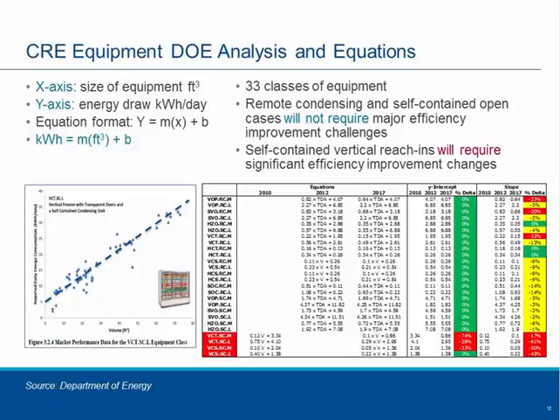Now, a best fit line on the scatter plot follows the format of y equals mx plus b, where b is your y-intercept that is on those kilowatt hours. The Department of Energy then looked at what the energy draw was as an aggregate for all these systems, and they basically drew another line that follows in parallel or with a slightly different slope, and that becomes your new equation that you apply to these pieces of applications. What I can tell you on this chart is that I looked at these 33-plus classes of equipment, and I wanted to compare what previous regulations were in terms of these equations, and analyze how much that y-intercept changes.